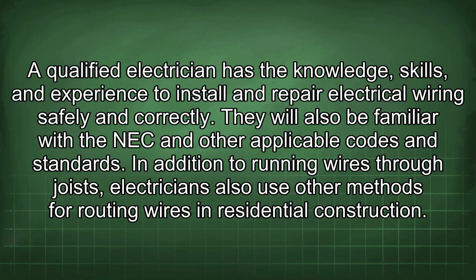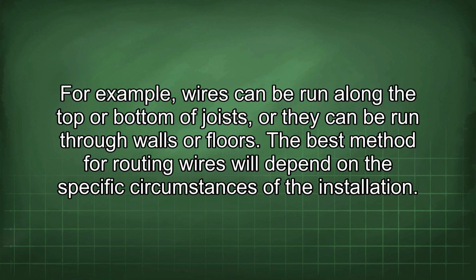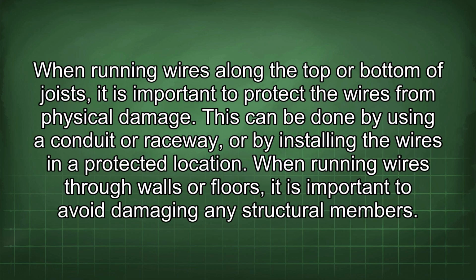In addition to running wires through joists, electricians also use other methods for routing wires in residential construction. For example, wires can be run along the top or bottom of joists, or they can be run through walls or floors. The best method for routing wires will depend on the specific circumstances of the installation. When running wires along the top or bottom of joists, it is important to protect the wires from physical damage. This can be done by using a conduit or raceway, or by installing the wires in a protected location.